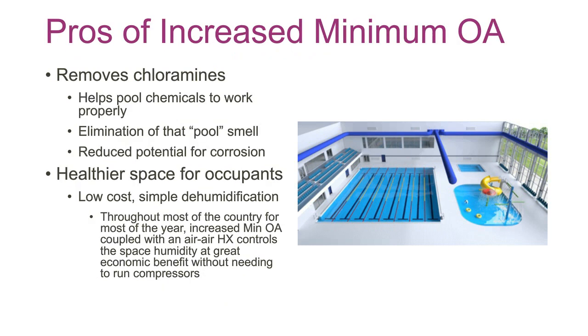So the pros of that certainly are it's going to remove more chloramines. That should help the pool chemicals work better, eliminate that pool smell, and help reduce the corrosion. Certainly healthier for the occupants. When people get in there, they feel good in the pool space, which has certainly not always been the case. And it's low-cost, simple dehumidification throughout most of the country for most of the year. Increasing the minimum outside air is going to control the humidity at a big economic benefit, and you're not going to need to run the compressors.